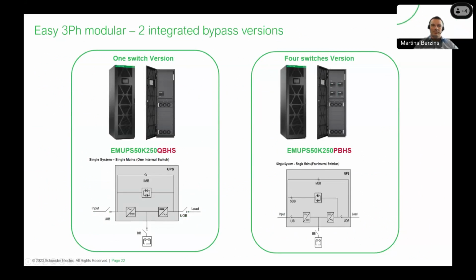Sure, I can explain shortly what makes a big difference. It's linked to a question of specifications. There is not a big difference between both, but as you can see on the single line diagram, it can be easier to operate the bypass when you have a 4 switch solution. It's quite similar in terms of functionality when you are using the single switch version. Why did we decide to launch 2 versions? It's more a question of specification requirements. Some tenders, we don't have the choice because we have this requirement coming from the specifier to have a 4 switch solution for manual bypass.